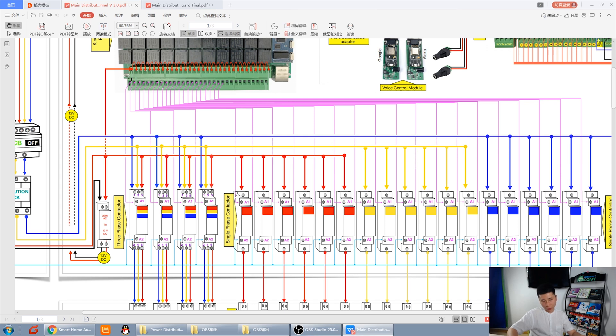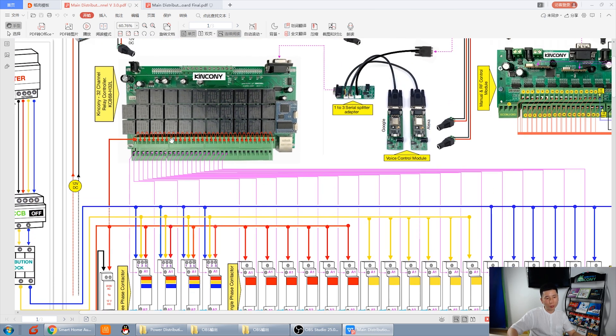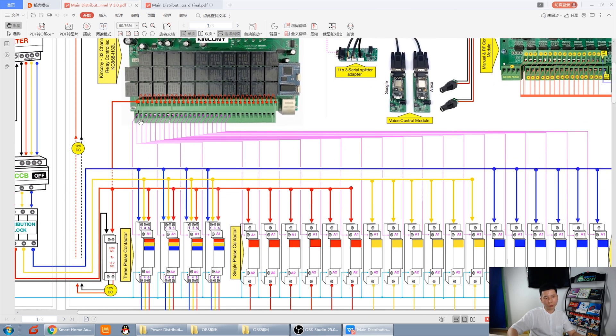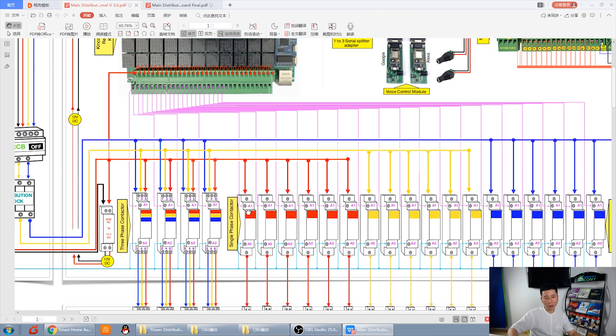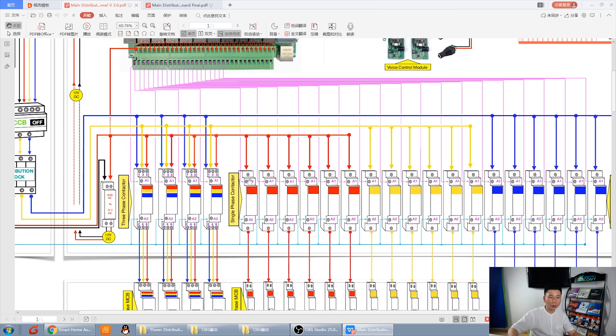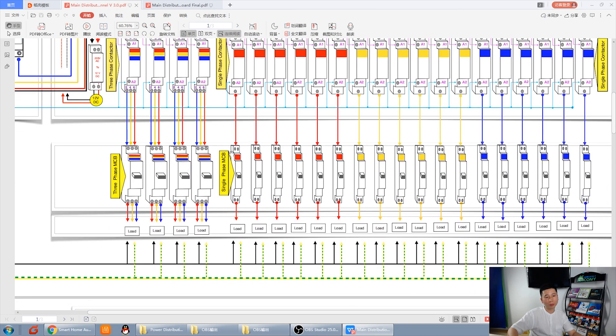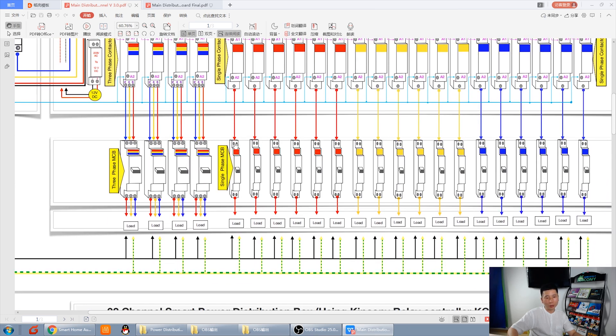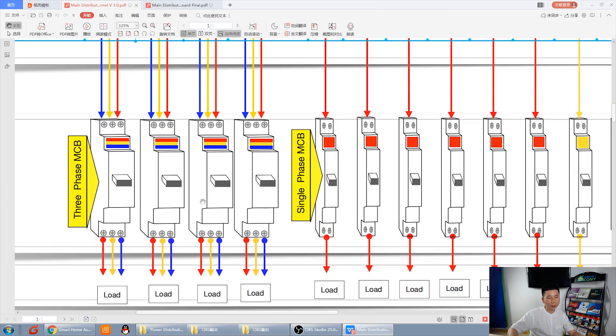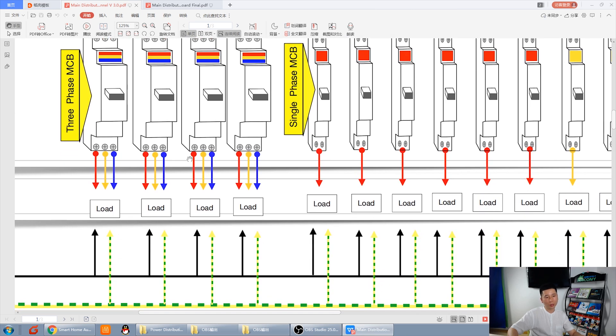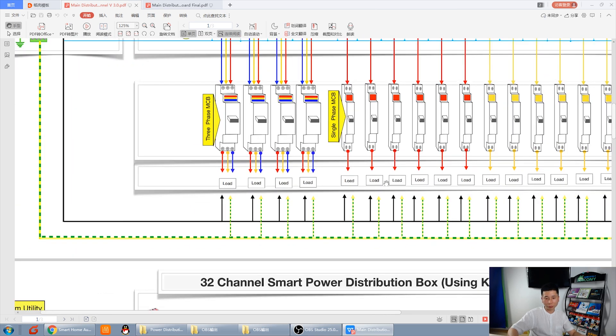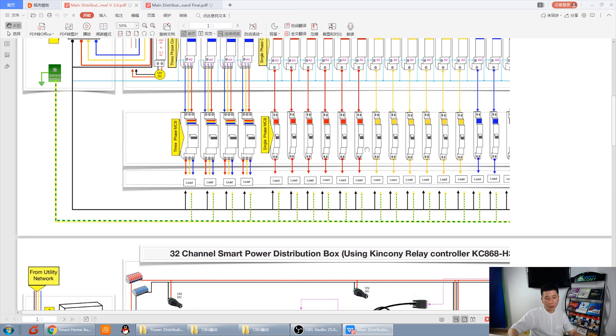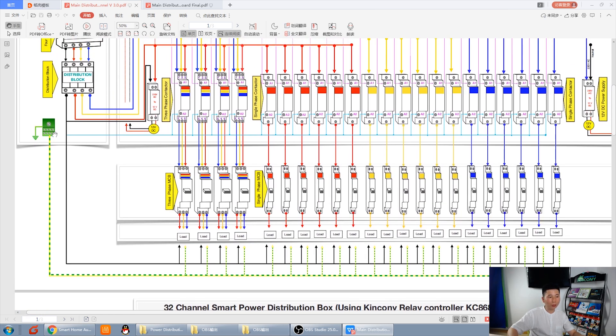When you use three-phase or use single-phase, how to control the AC contactor turn on and turn off? Just use relay control. Output a signal for 220 voltage to the AC contactor. Then, the AC contactor will be closed. When AC contactor closed, the power will flow to the breaker. So, this is a breaker. This breaker also has two kinds. This is a three-phase breaker. And this is a single-phase breaker. And output as a breaker, you can connect with your electronic load. So, at last, this is the earth. The earth line.